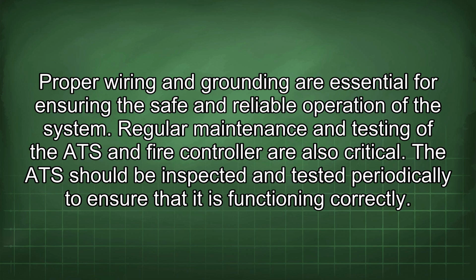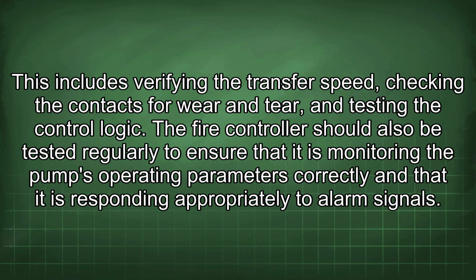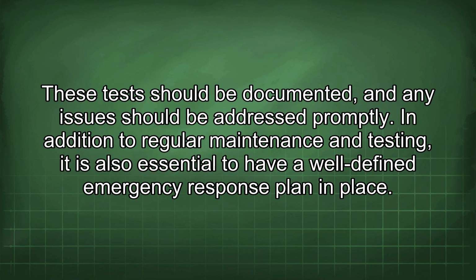The ATS should be inspected and tested periodically to ensure that it is functioning correctly. This includes verifying the transfer speed, checking the contacts for wear and tear, and testing the control logic. The fire controller should also be tested regularly to ensure that it is monitoring the pump's operating parameters correctly and that it is responding appropriately to alarm signals. These tests should be documented, and any issues should be addressed promptly.